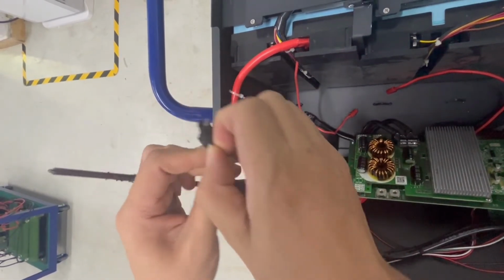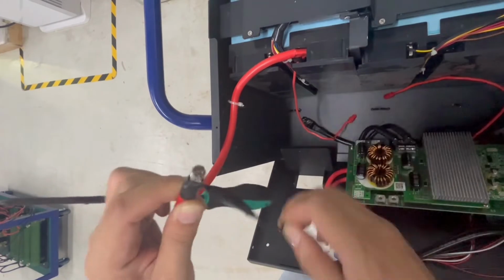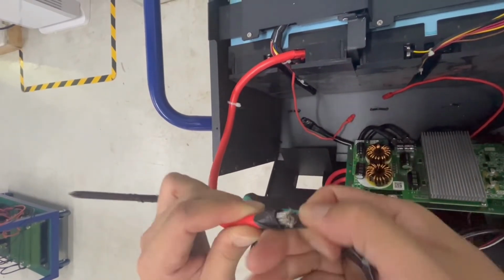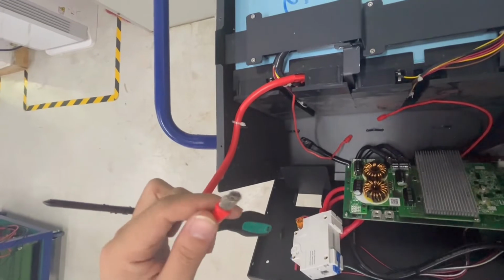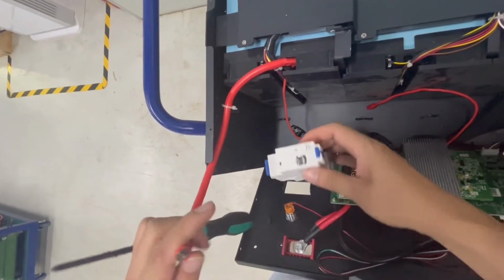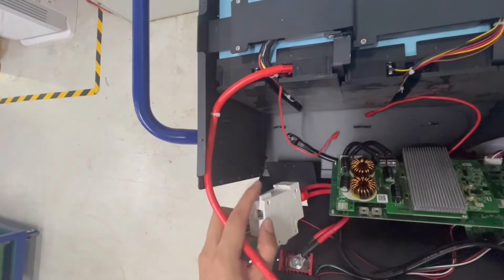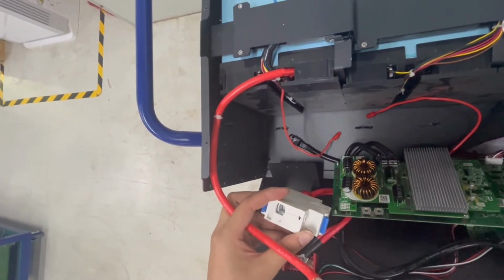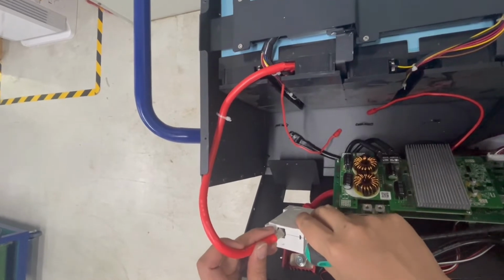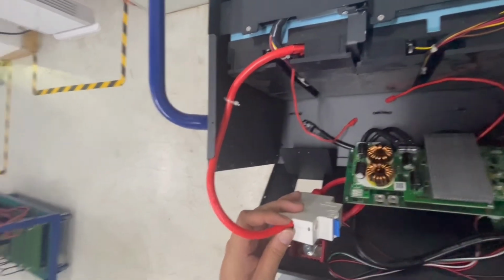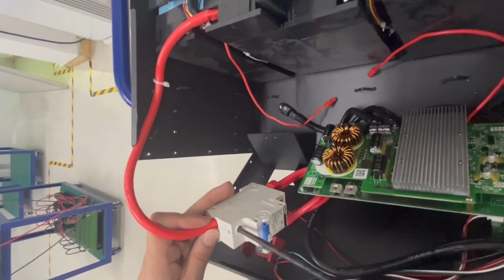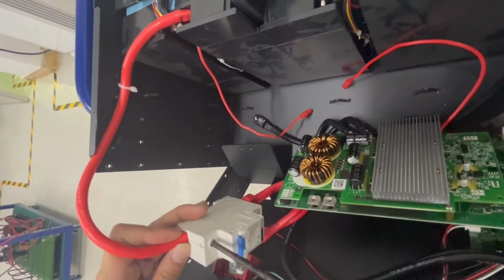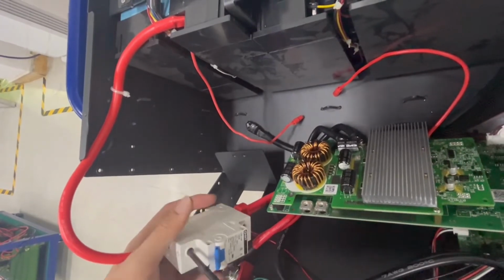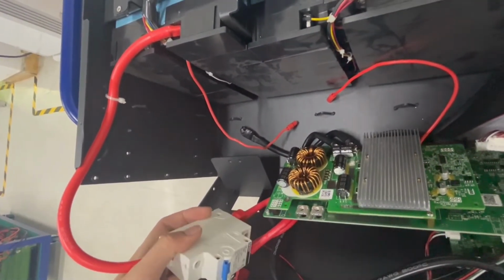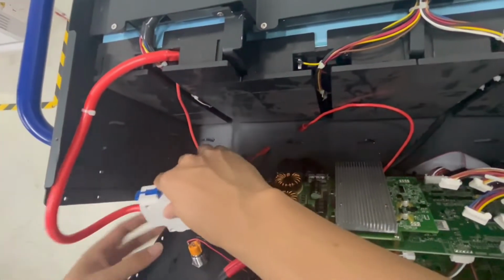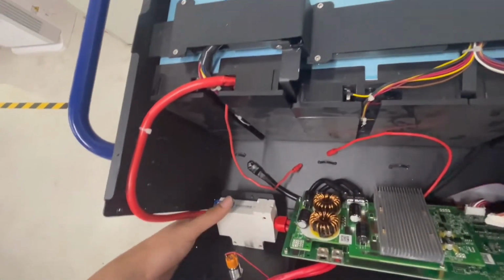If you want to communicate with MPP Solar, you can connect to the RS485 port of the BMS. It is also by default loaded with the protocol compatible with MPP Solar, named Pylon 485. Once you want to communicate with MPP Solar, just connect through RS485 to the inverter, and on the inverter side, set the battery type to lithium, accordingly Pylon PYL.